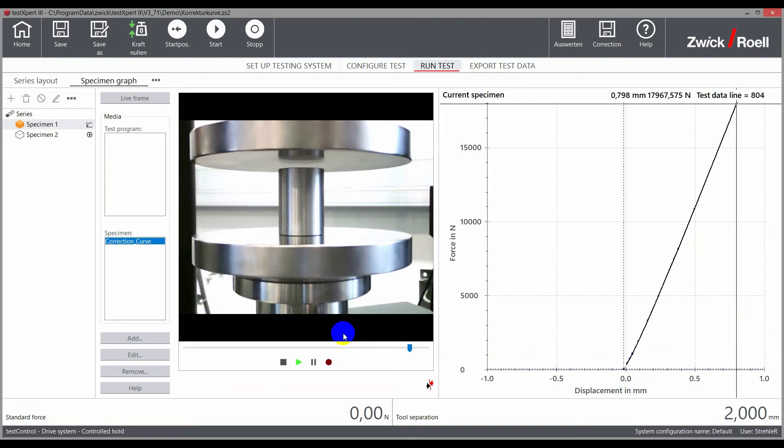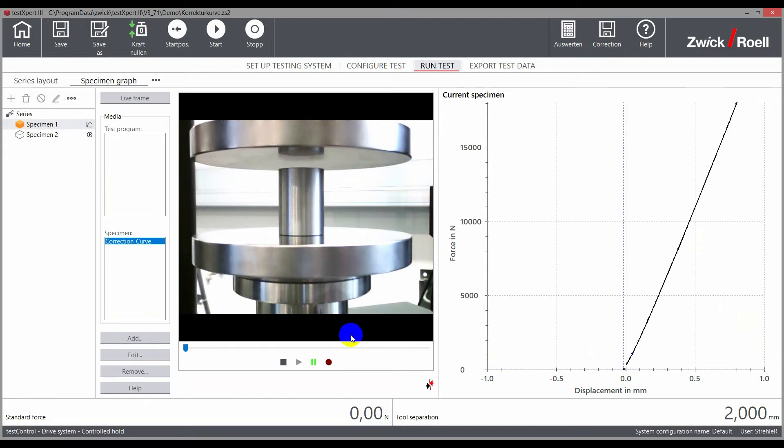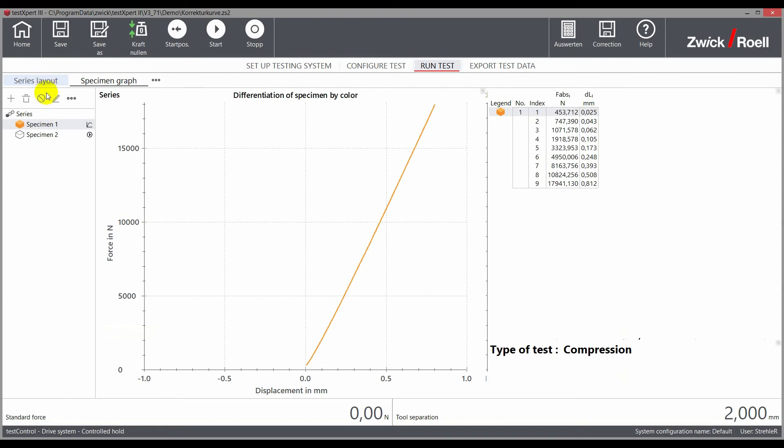From this measurement, testXpert 3 determines a correction curve that is stored in the test control machine electronics. This correction curve is then used for every test to correct the deformation of the test arrangement and to position the testing machine on corrected targets. This correction is applied during the test in real time.